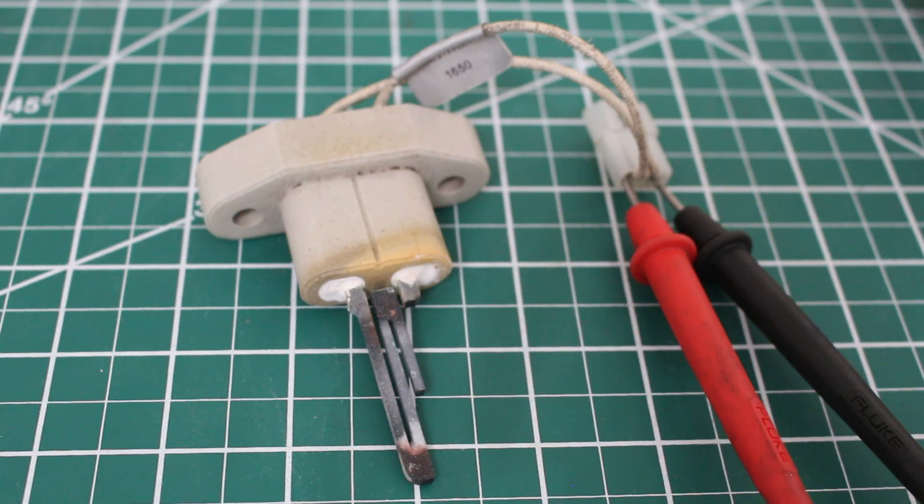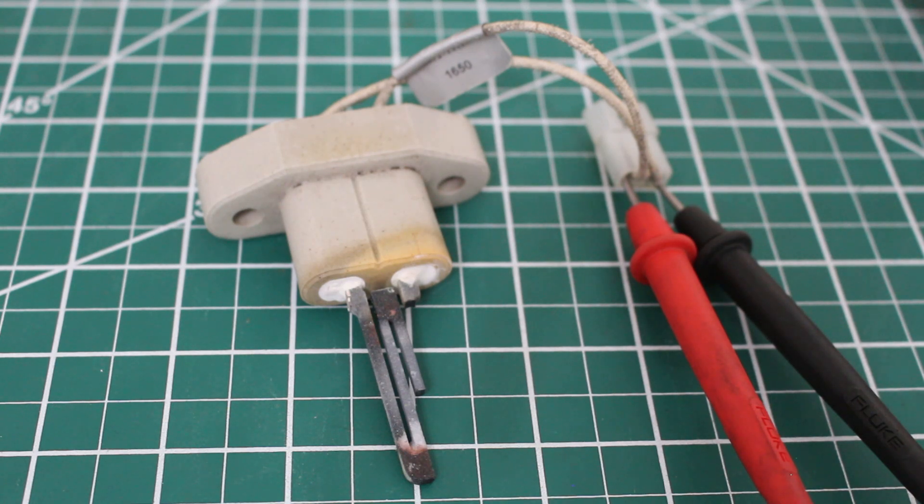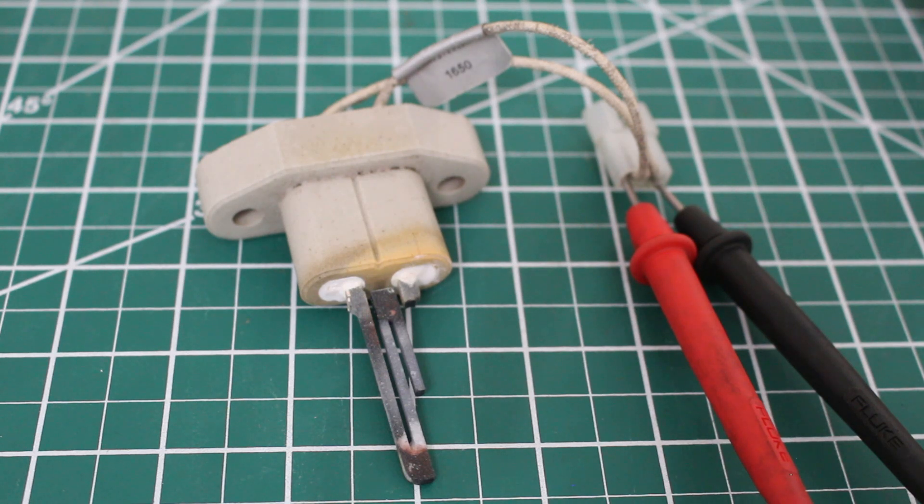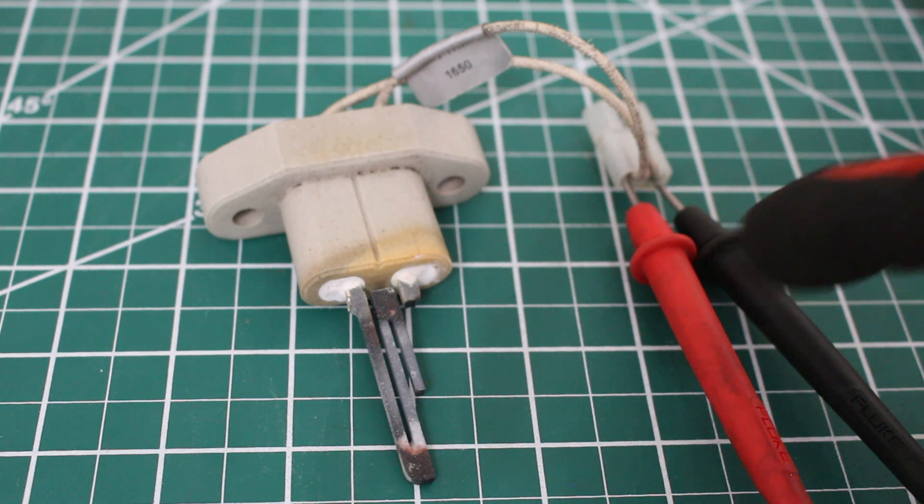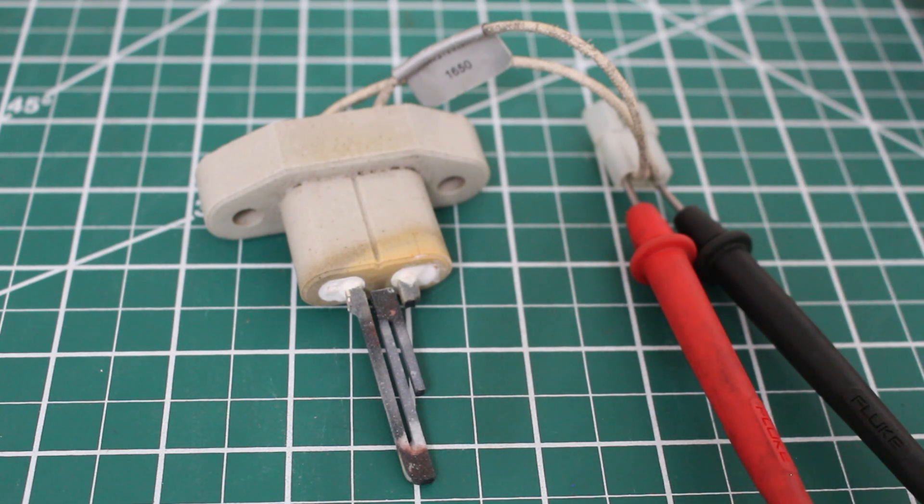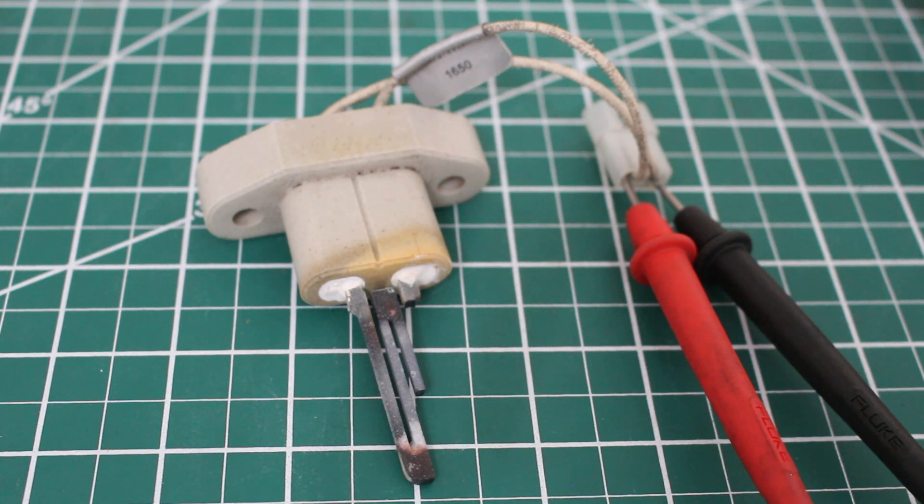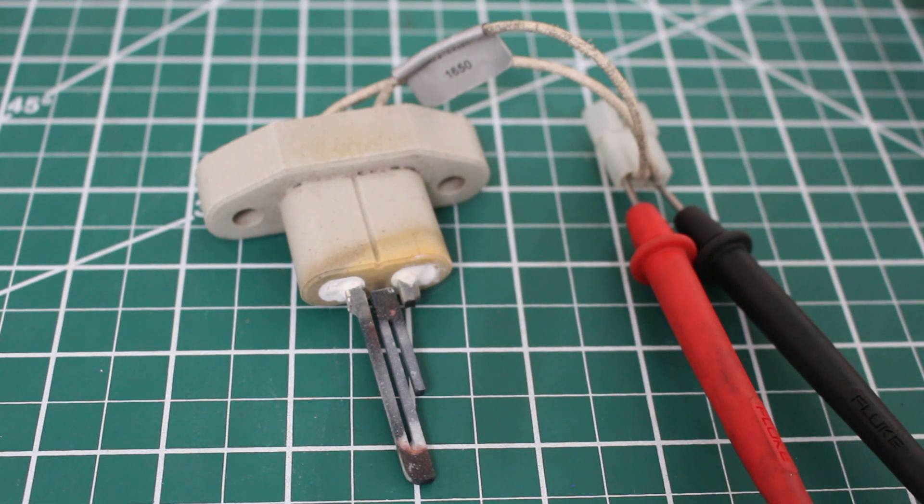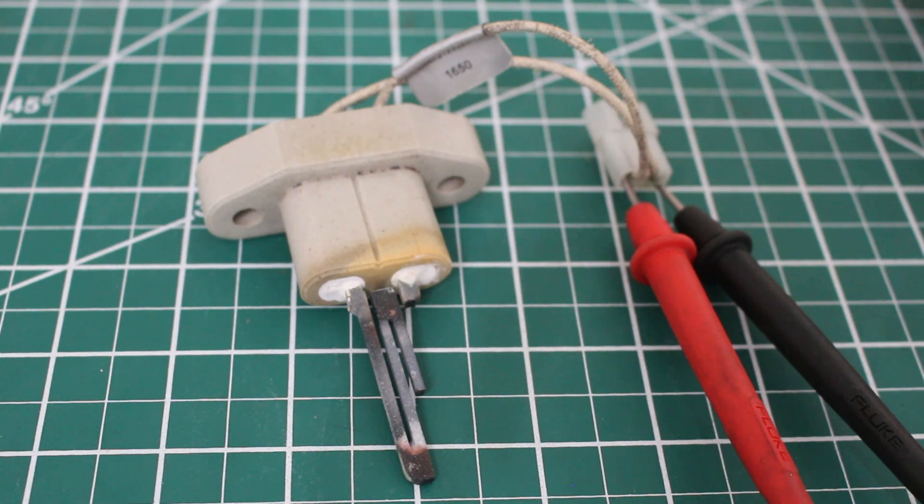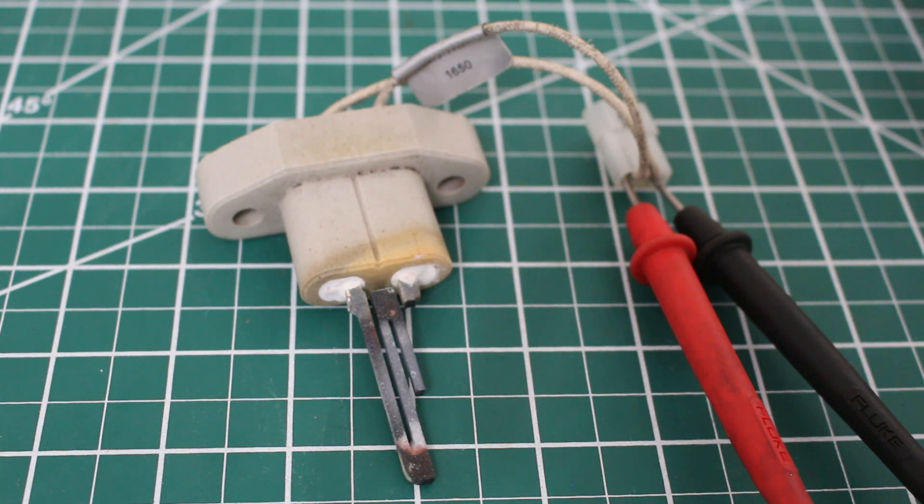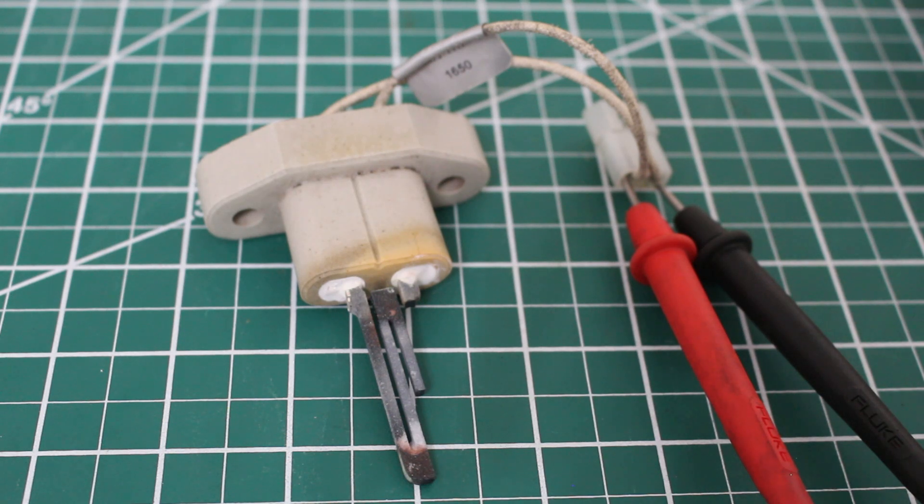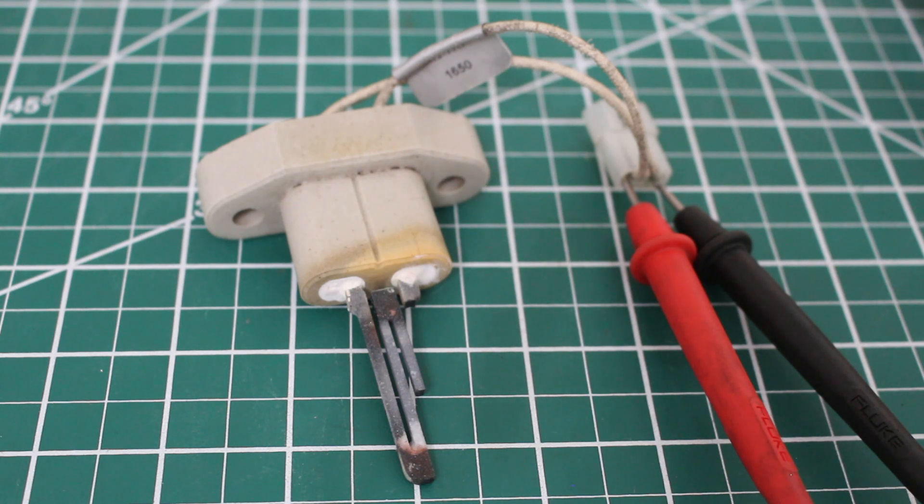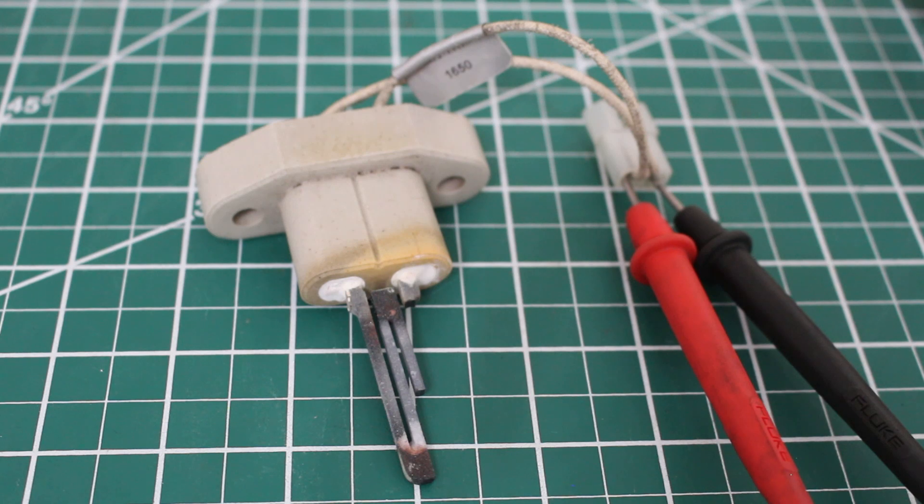This here is my preferred method by checking voltage. So in this case we'd have the power onto the system. Everything would be connected. We would find a place where we can connect our two leads from our meter so we can read voltage across the two conductors. So if we get the correct voltage applied to the hot surface igniter it's important to look through in the burner section because it's usually a little area where you can actually see if we have a flame and in the same place you're going to see the hot surface igniter. So if we get the correct voltage to the hot surface igniter and it doesn't glow then you know it's bad.